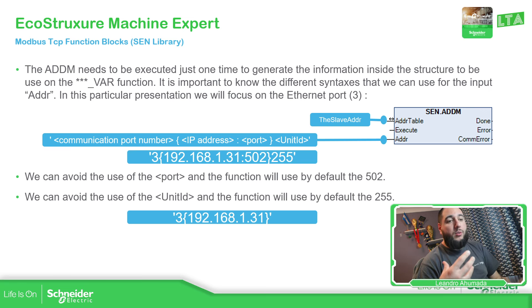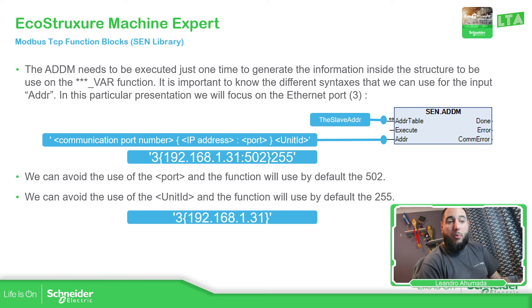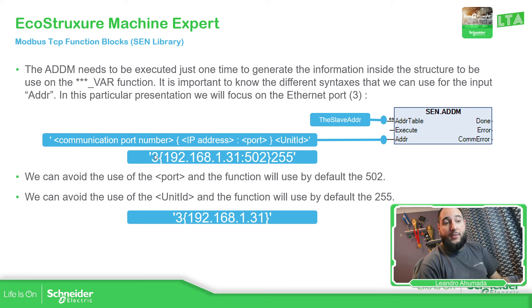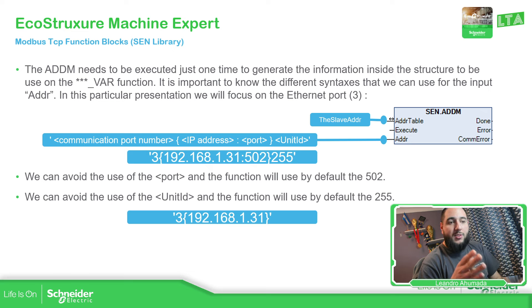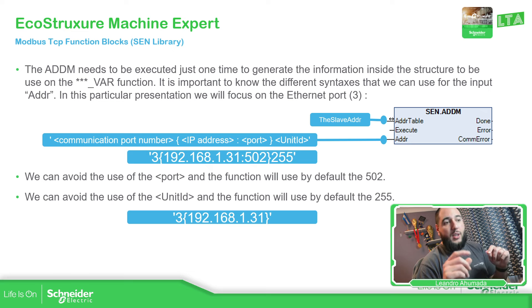Depending on how we are going to communicate to the device, the syntax that we need to use is different. In this particular case, as we are using the Ethernet port, we just need to use communication port number three. If you're going to use Modbus Serial, we just need to use the number one. For Modbus TCP, we just need to use number three, and between the curly brackets, we just need to use the IP address.